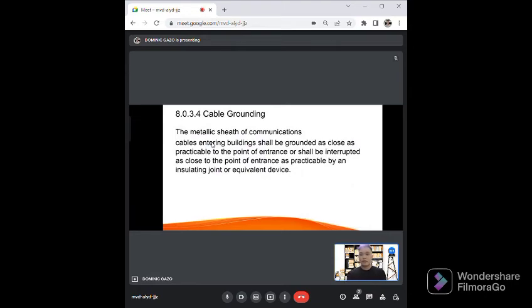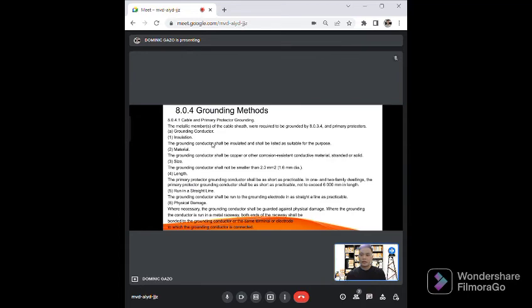For 8.3.4, for cable grounding, the metallic sheath of communication cables entering buildings shall be grounded as close as practicable to the point of entrance, or shall be interrupted as close to the point of entrance as practicable by an insulating joint or equivalent device.